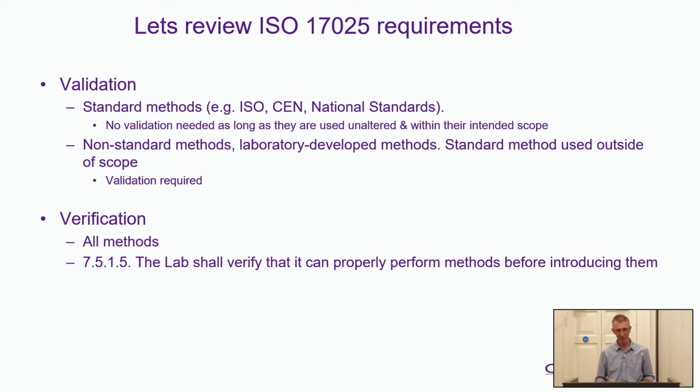So if we view those 17025 requirements in more detail, for validation, you've got to use standard methods like ISO and CEN methods, and those methods don't need to be validated as long as they're used unaltered and within their intended scope. That's what 17025 is saying. If you're using an ISO method properly, then that doesn't have to be validated. It's already taken to be valid.